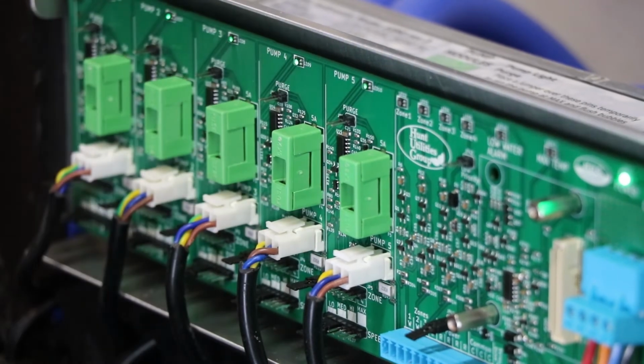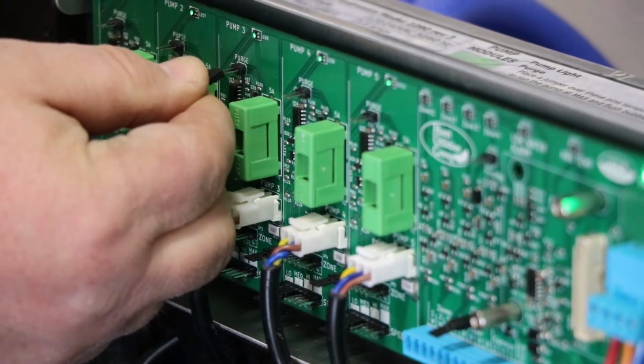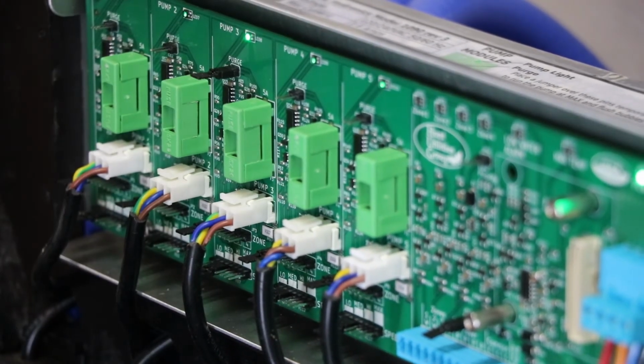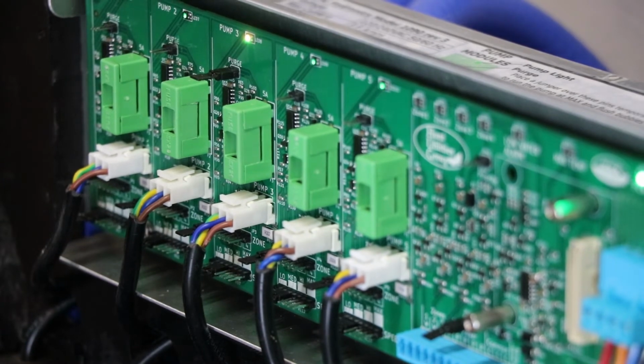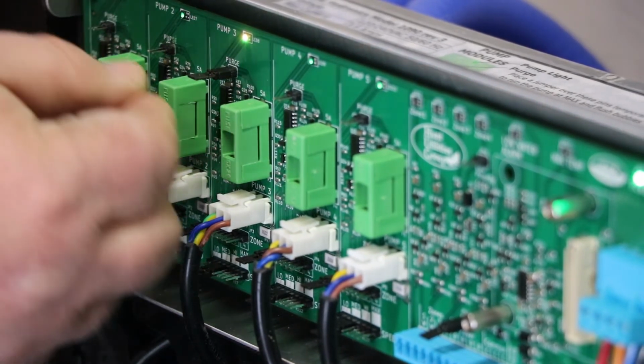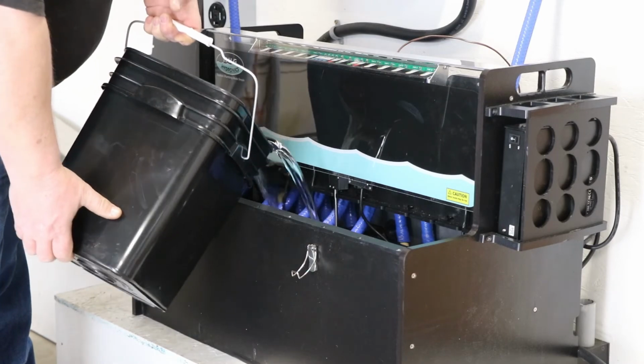Repeat the purging for each pump that is in use. And a reminder, only purge one pump at a time. The water level in the tank will drop during this process, so add more water glycol to the tank as needed.